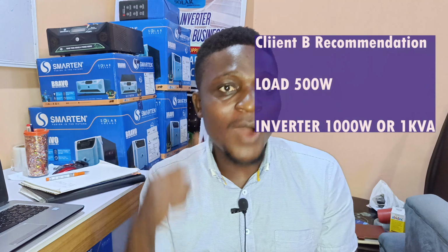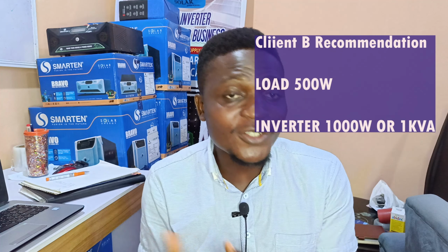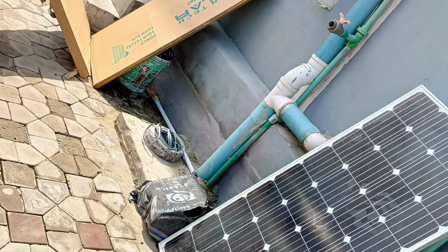Let me break it down properly. Client B, with a 500 watt load, should have opted for a 1 kVA inverter, which would work perfectly for his setup, instead of going for a 2 kVA or higher just because his friend uses the same. The point is that when sizing an inverter, you must size it relative to your load.